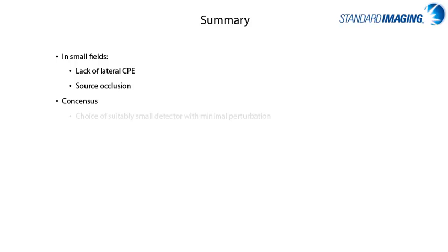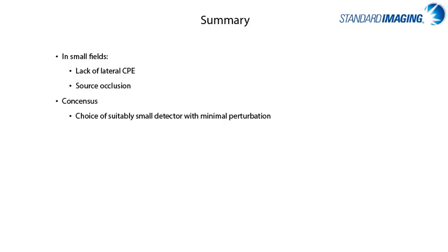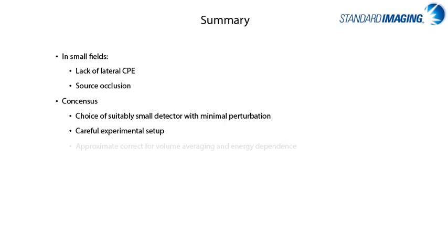For making measurements in small fields, the consensus is to ensure that you have chosen a detector that is suitably small and has minimal perturbation effects. Ensure that your instruments are carefully set up and double checked. Also, ensure that the correction factors for volume averaging and energy dependence have been determined for whatever dosimeter you are working with, if they are applicable.